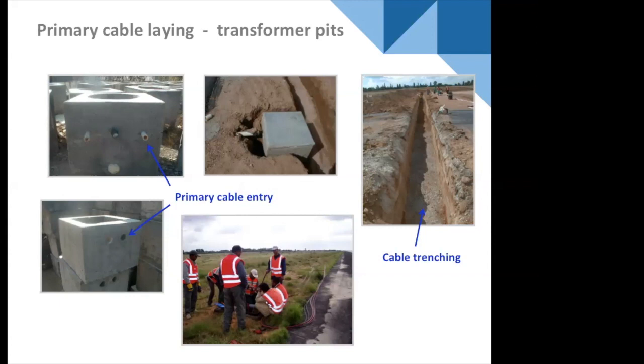We install the cabling in the field, and we put the appropriate connectors, primary connectors, onto the cabling to be able to connect together. And that is a major installation issue, basically, because if I've got a runway centre line and I need to get the secondary cable from a transformer pit out to the light fixture, I've either got to decide: do I put it in ducts, onto the pavement, or do I cut a saw cut across the pavement? So whatever the design is, we have to decide what we're going to do.